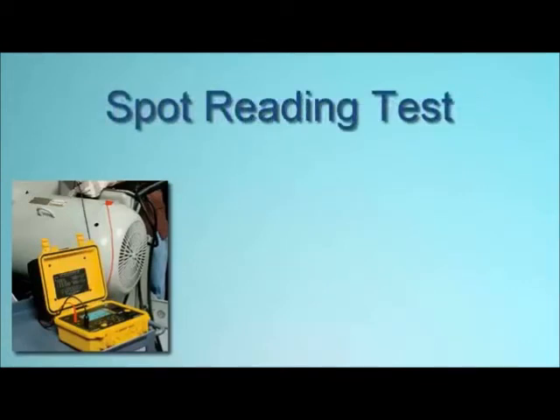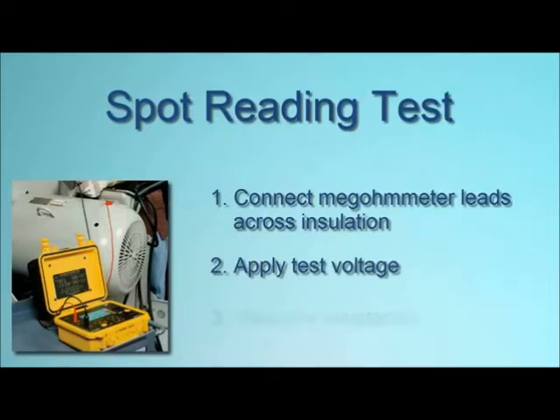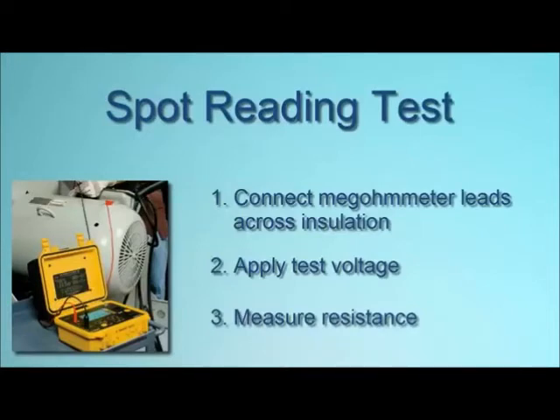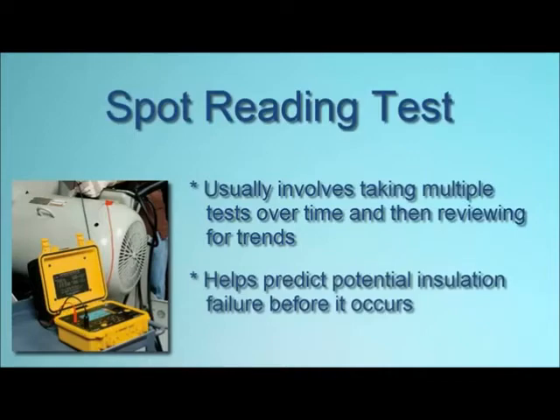The first type of insulation resistance test we'll look at is the spot reading test. This is relatively straightforward: simply connect the megohmmeter leads across the insulation to be tested, apply test voltage for a fixed period of time — typically 1 to 10 minutes — and then take a resistance reading. Spot testing is suitable for a system with small or negligible capacitive effect, for example a short wiring run. A single spot reading test is of limited value, but the results become meaningful when a series of tests, all featuring the same voltage and duration, are performed over time and the results compared. This comparison can help predict a potential insulation failure in time to take corrective action.